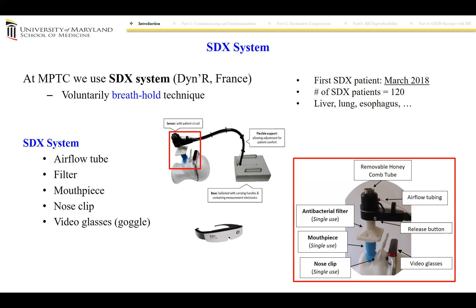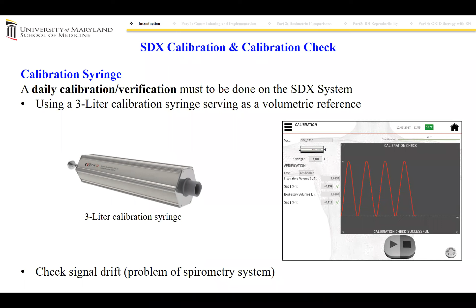When you look at the SDX with the ProBeam connection, we have the patient in the room with the SDX system, and the SDX system is connected with an Ethernet cable to the computer, which is connected to the SDX gating module, and that is connected to the ProBeam gating module, which controls the beam. We do a daily calibration check, and sometimes we do the calibration if we use a different honeycomb tube or we clean the honeycomb tube. For the calibration check, we use a 3-liter calibration syringe. We pump the syringe, we know its actual volume, and we have a tolerance for that. If it fails the check, we perform the actual calibration. This helps check the signal drift and correct it if it's off.